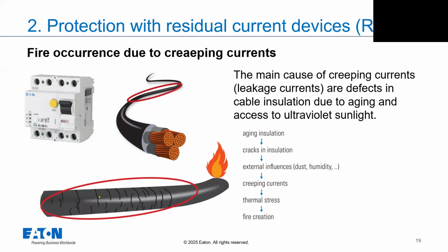Historically, there was some research on how to prevent fires in installations, for example, where we have cables mainly with PVC, polyvinyl chloride, which are the most used. The problem is that with ultraviolet or higher temperature and so on, damage is created on the surface, and a combination of dust, humidity, and external influences creates creeping currents. Then with this creeping current between phase and ground, for example between phase and wood, local heating with thermal stress starts, and fire can be created.